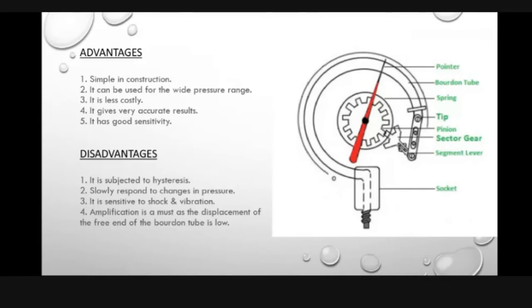As we know, every machine has its instruments and has its pros and cons. Now we are going to see the advantages of the Bourdon tube. First, it is simple in construction and easy to assemble. Sorry everyone. It is used for a large pressure range. It is very affordable. As Pooja told at the start, it gives the measurement accurately. Second, it has good sensitivity.